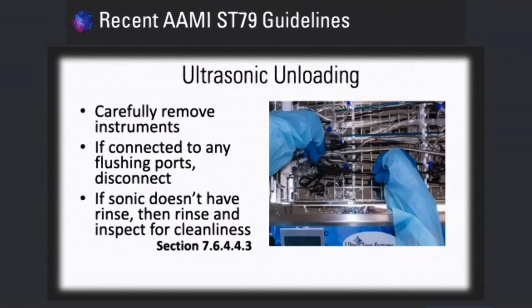Ultrasonic unloading. Carefully remove instruments. Yes. Don't damage your instruments and don't damage yourself, okay? Take it easy. I know it's hard to follow through on that because you guys are so busy. If connected to any flushing ports, disconnect. Again, you're busy, you might want to rip the instruments right out of the machine. Just take your time if you can, or methodically remove them. And if the sonic doesn't have a rinse, then rinse and inspect for cleanliness. Now, there's a lot to be said about verification.